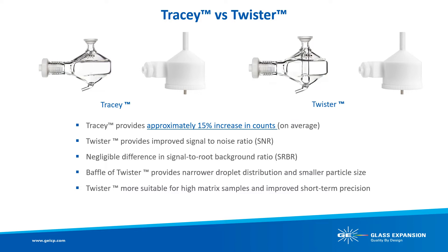The Tracey is a single-pass cyclonic spray chamber, noticeably different from the Twister design which features a central baffle. With routine aqueous samples, we do not need to be concerned with matrix effects from high concentrations of dissolved solids. We want to maximize the efficiency of sample transport and washout, and with no hydrofluoric acid present, we can use a glass or quartz spray chamber.